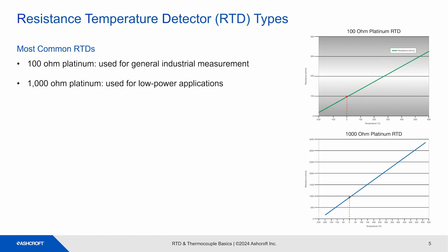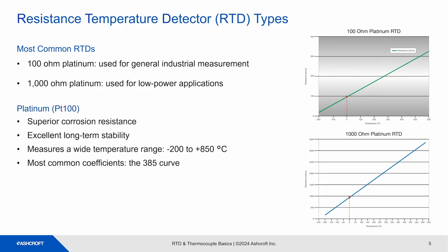C. The reasons we use platinum are superior corrosion resistance, excellent long-term stability, measures temperatures over a wide range of minus 200 to plus 850 degrees. The most common coefficients are the 385 curve. Other RTD types, like nickel or copper, are used in limited applications.